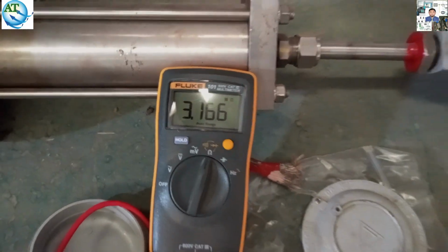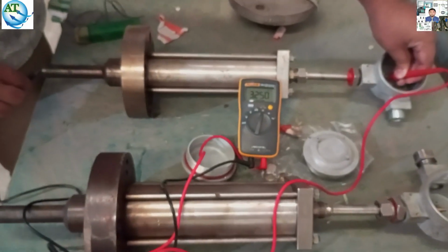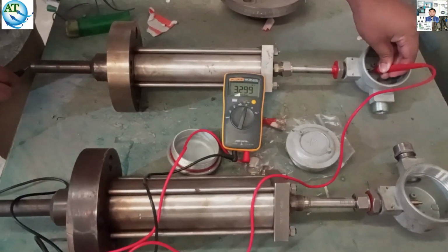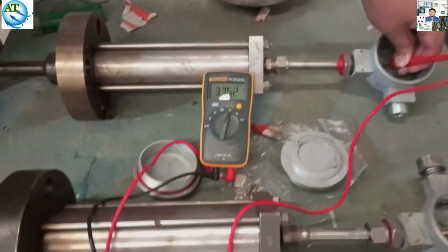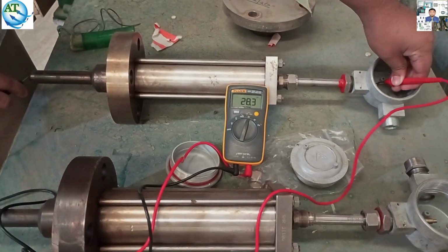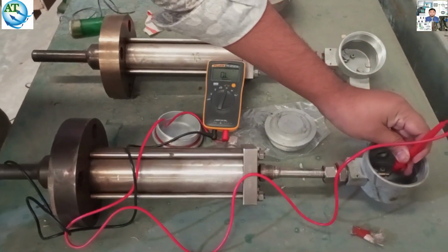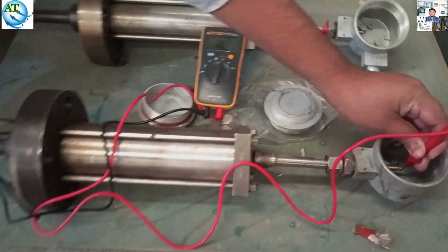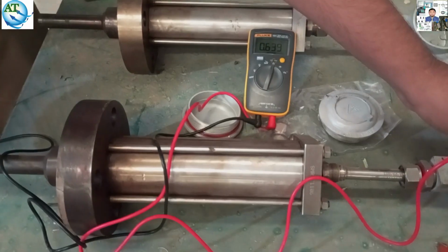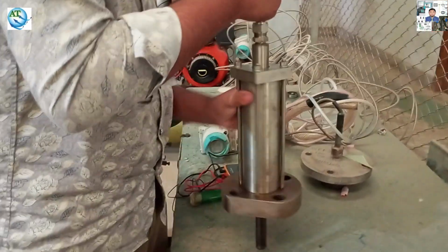It is a single rod. One side is connected, and with the multimeter, one probe is on one side and the other probe is on the other side. That means it is a single rod. If we connect this single rod, then we should find 0 ohms, or 0.12, 0.34 ohms or something. But we find that it is mega ohms. That means the middle section of this rod is damaged, so we are getting mega ohms or giga ohms.